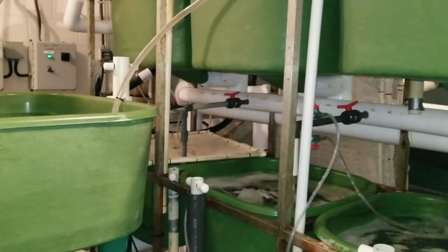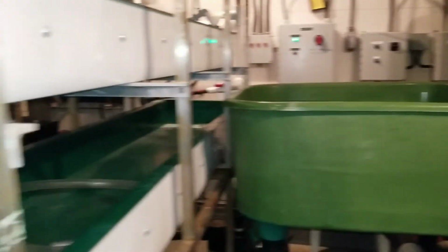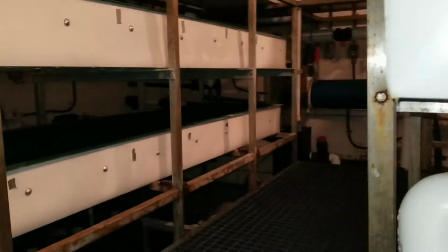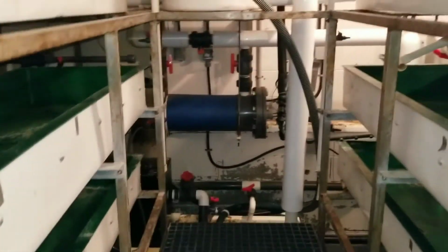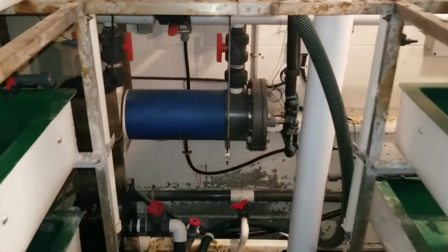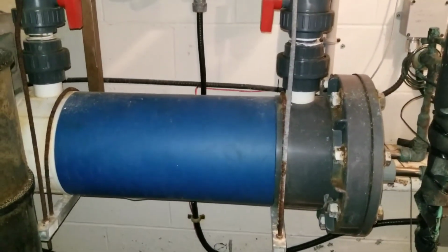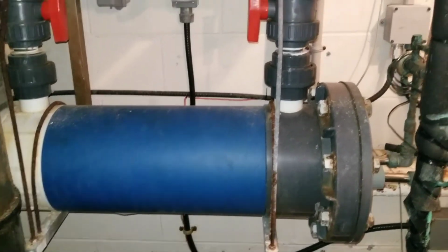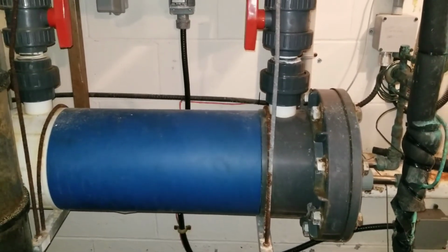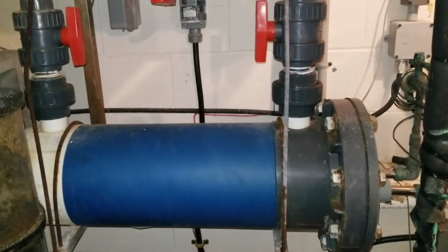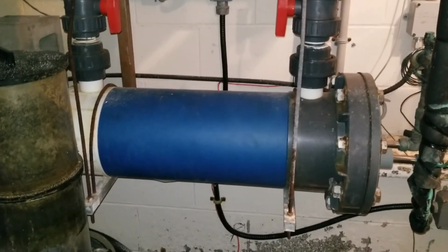We do, however, have very good temperature control in these systems. When we refitted this system a few years ago, we actually replaced our heat exchangers with high-end and high-capacity titanium heat exchangers, like the one you can see here in front with the blue insulation on it. And the heat pumps that provide the heating and cooling are actually oversized for these size of systems. So we have a very high capacity to control temperature.